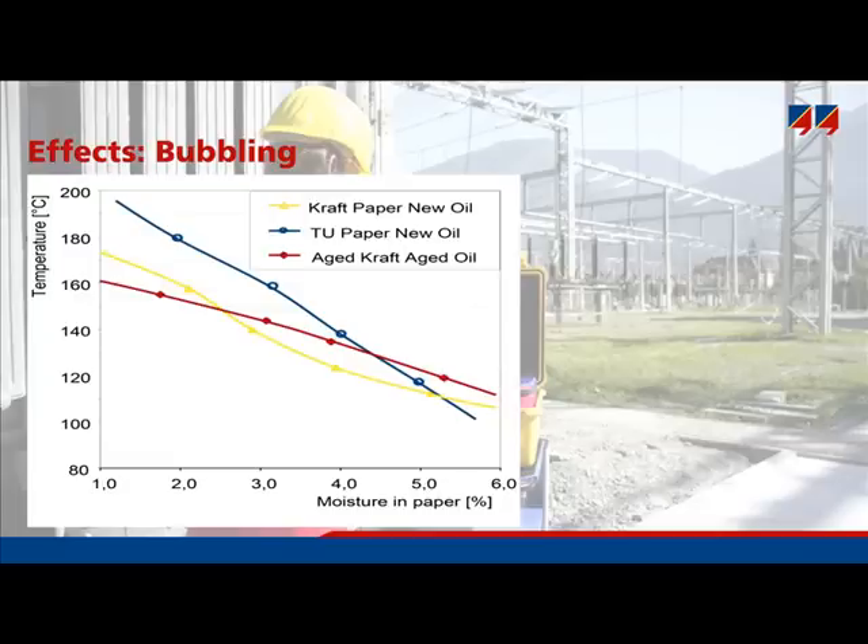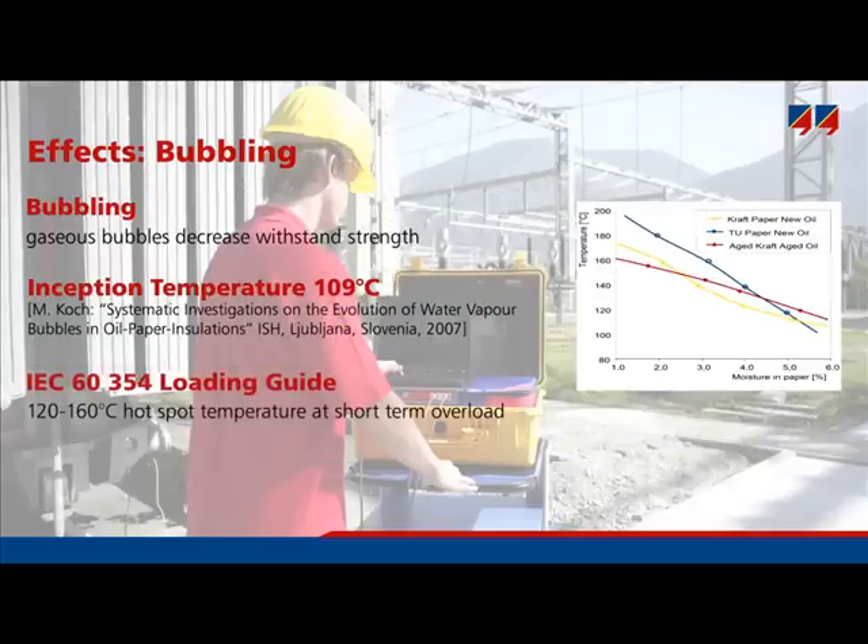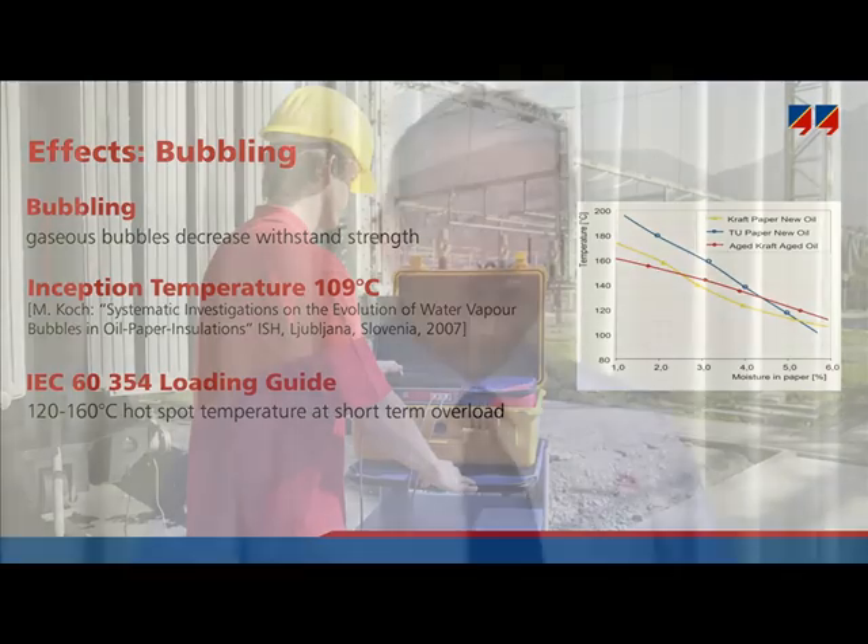Even for a rather dry transformer with around one to two percent moisture content, bubbling can be expected. Since the IEC loading guide for oil-immersed power transformers allows for a short-term overload of up to 160 degrees centigrade, bubbling really is a concern for wet insulation systems.